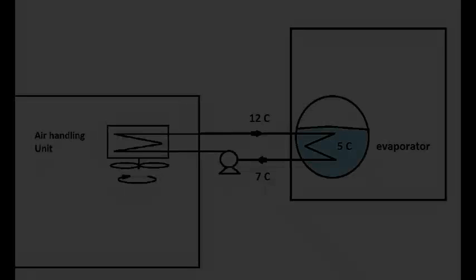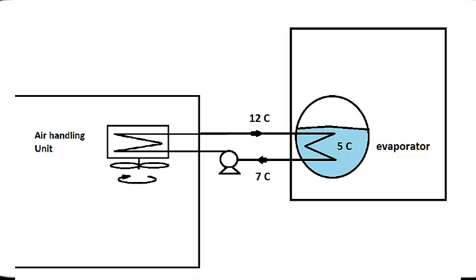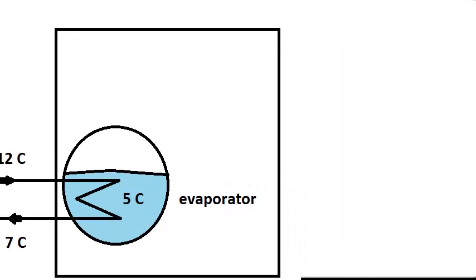In the system we will be studying, the heat transfer fluid is pumped through another set of coils in an evaporator vessel containing water at such a low pressure, under 1/100th of an atmosphere, that it boils at 5 degrees C. All the thermal energy that the heat transfer fluid picked up in the air handling unit is passed into the water in the evaporator, causing it to boil.